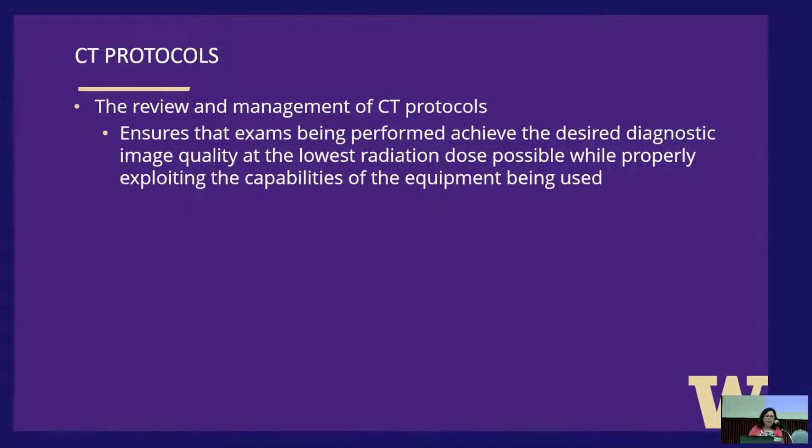So review and management of CT protocol ensures that exams being performed achieve the desired diagnostic image quality at the lowest radiation dose possible. And actually I would like to scratch the word lowest and replace it with optimized radiation dose. We are not trying to go low, which is what Dr. Brady likes to do at his hospital, but we want to be optimized dose. What is the best dose for this task? Doesn't mean it has to be the lowest dose, while properly exploiting the capabilities of the equipment being used. So that is incredibly important.